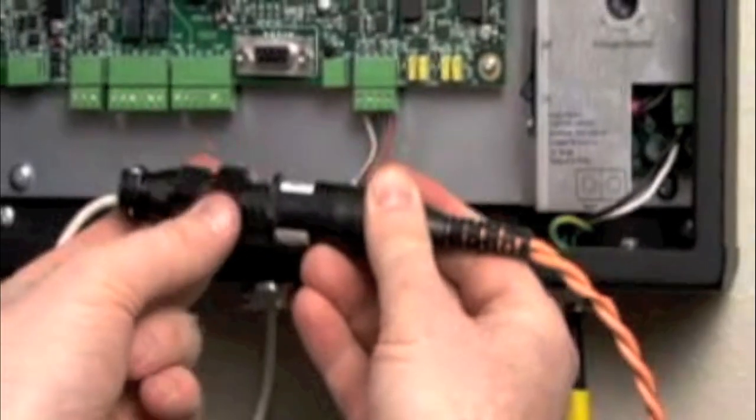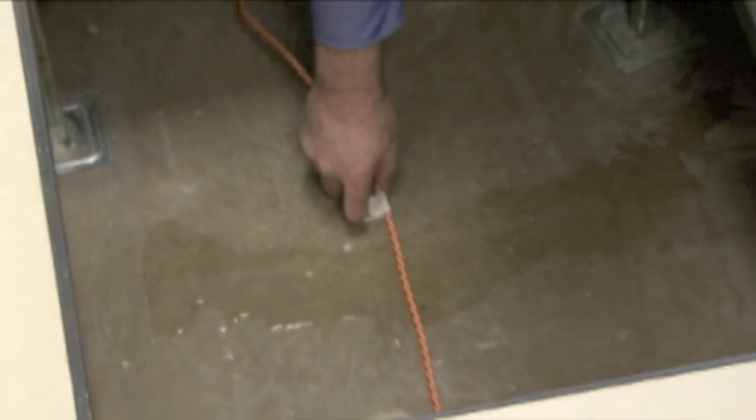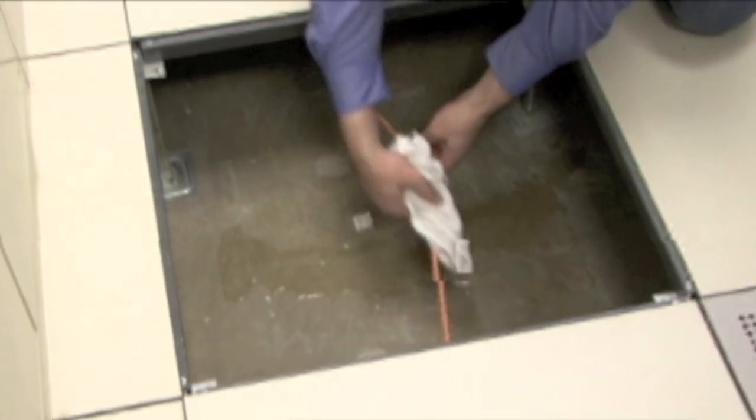When tied to a single-zone controller, you're going to identify that water is on the cable, but not the specific location. That works great in an area where you can walk in and see exactly where the problem is, quickly identify the issue, and resolve it. It is a quick-dry, quick-reset cable — you can identify the issue, literally wipe the cable off, and it's ready to detect another issue as quickly as it went into an alarm condition.